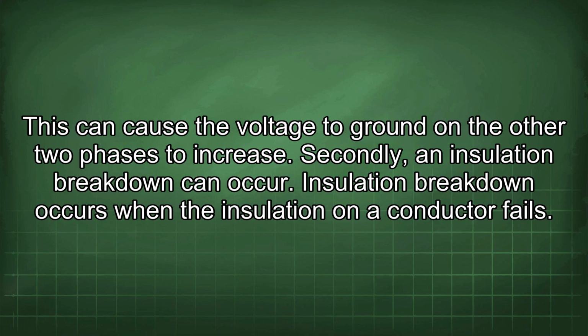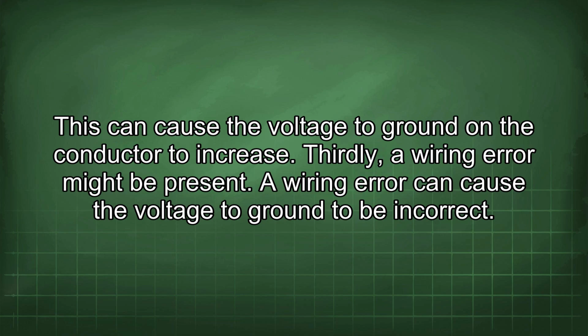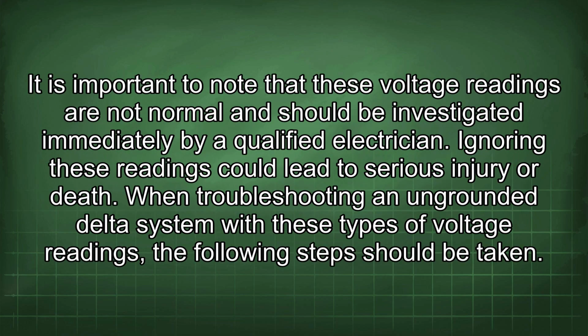Secondly, an insulation breakdown can occur. Insulation breakdown occurs when the insulation on a conductor fails. This can cause the voltage to ground on the conductor to increase. Thirdly, a wiring error might be present. A wiring error can cause the voltage to ground to be incorrect. It is important to note that these voltage readings are not normal and should be investigated immediately by a qualified electrician. Ignoring these readings could lead to serious injury or death.